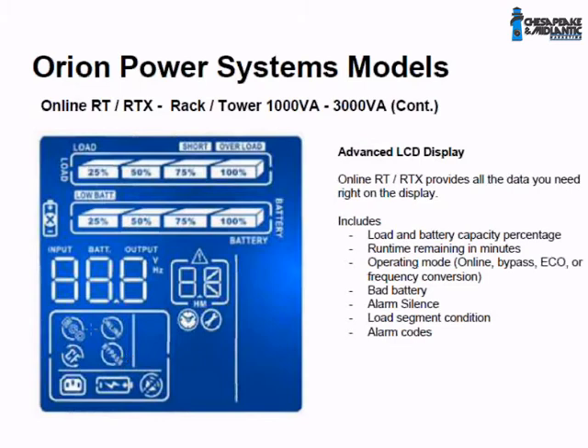It also has an eco mode. If you're in an area with super clean power, you can put it in eco mode, and it will run like a standby UPS—essentially running in bypass, then switching to battery when it sees an outage. Realistically, I doubt most people will use that, but it's there. It can also do frequency conversion, converting from 60 to 50 hertz, though that's an odd application I doubt will be used much.